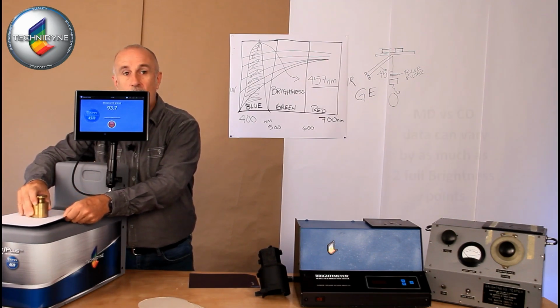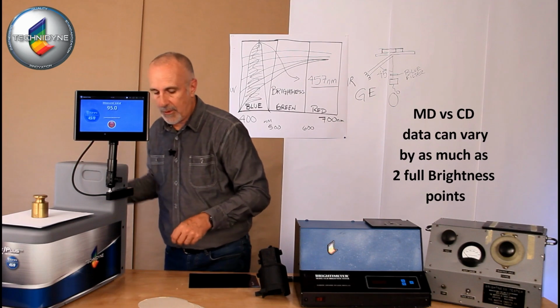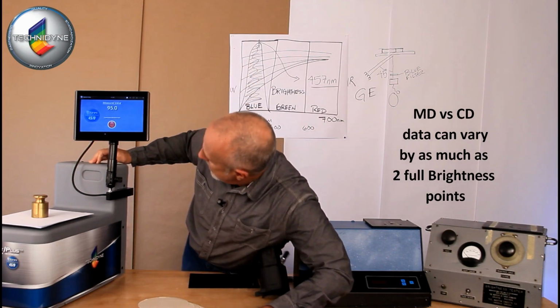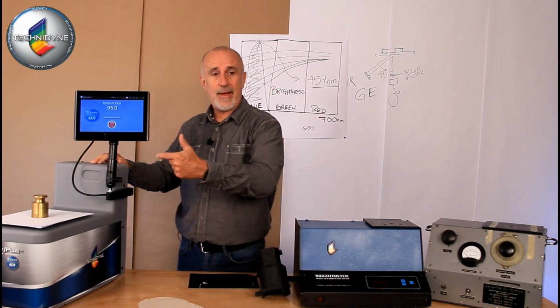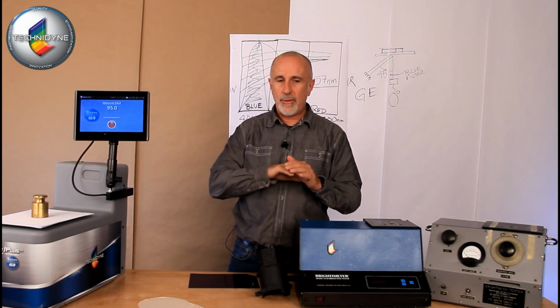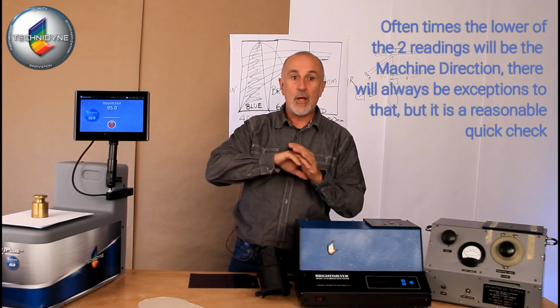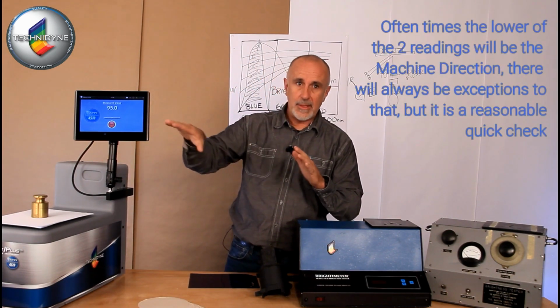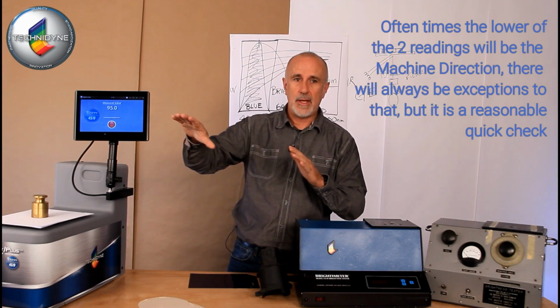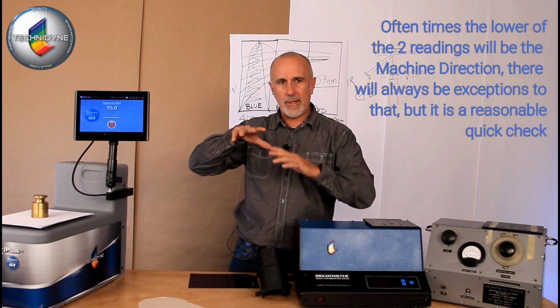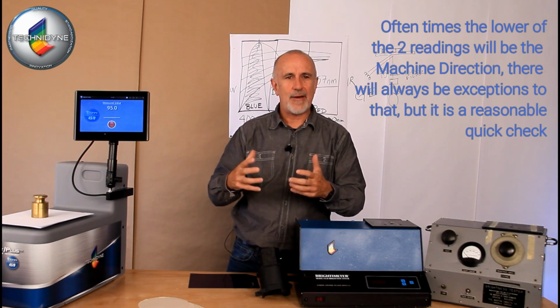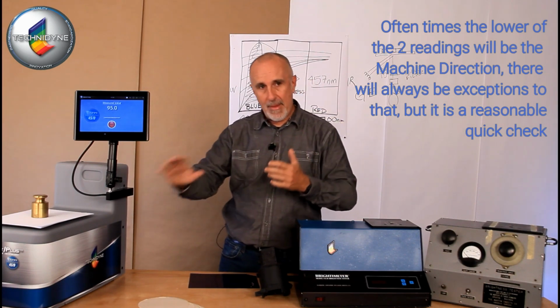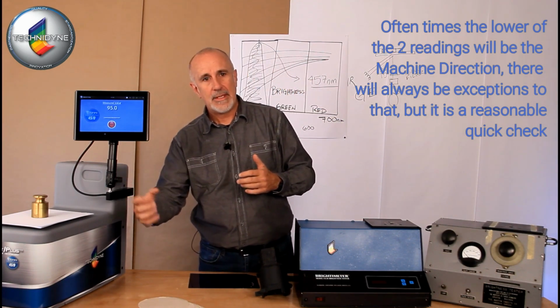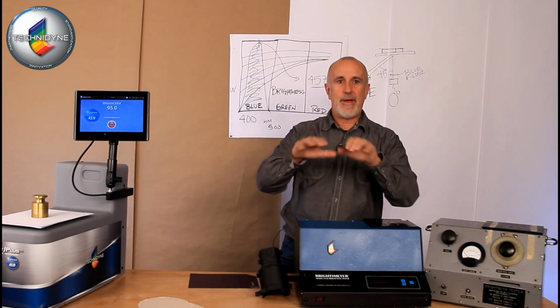So now I'm going the opposite direction as far as the fiber orientation. And now the measurement is 95. Always, as a rule of thumb, you can assume that the lower of the two is going to be the machine direction. Otherwise, the fibers are going to be oriented in the opposite direction. You'll get more scatter from that, and you'll get a higher number. But the method calls to measure the sample in the same orientation as the fibers are.